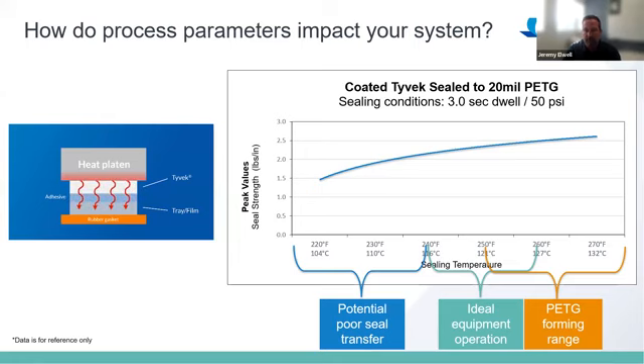And then on the right is a seal curve. For those of you that aren't familiar with a seal curve, this is a way to profile different material combinations at different temperatures. In this case, we're keeping the sealing conditions at 3 seconds time and 50 PSI gauge pressure, and we fluctuate the temperatures. At the low end, with this particular coated Tyvek, you're still getting a pretty good peel strength value, about 1.5 pounds per inch at the 220 Fahrenheit set point. But at that point, you may get poor seal transfer. So even though you're getting a good peel strength, it may not be a full seal. And at the high end, you may run into a little bit of over processing. So again, it's important to know both sides of the seal curve for the adhesive.